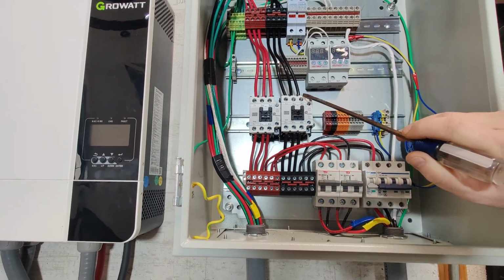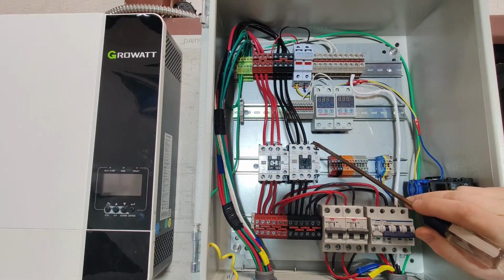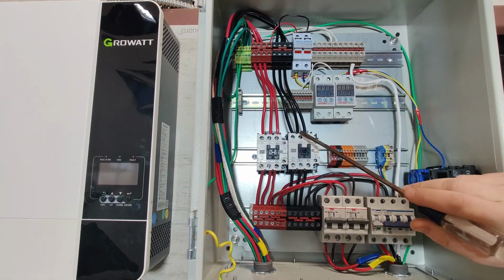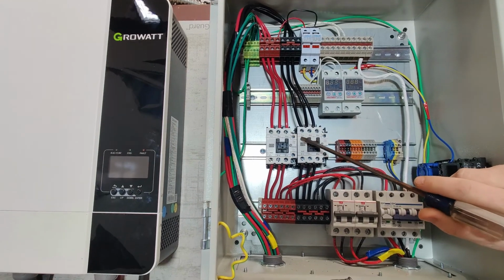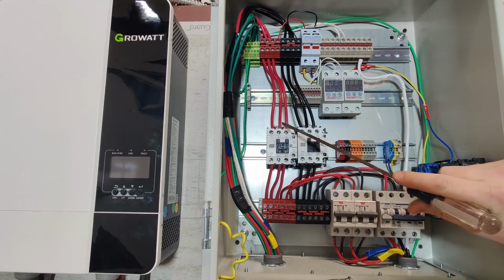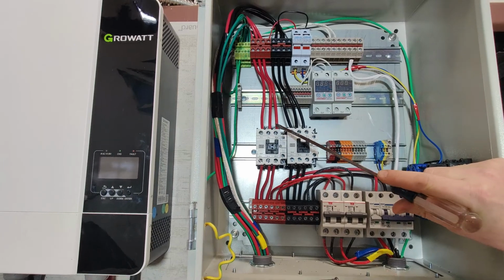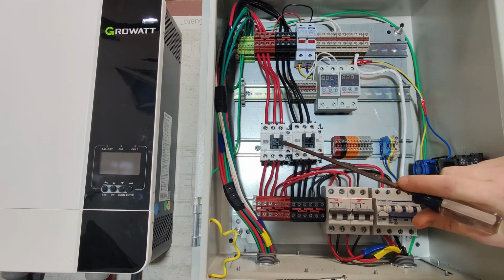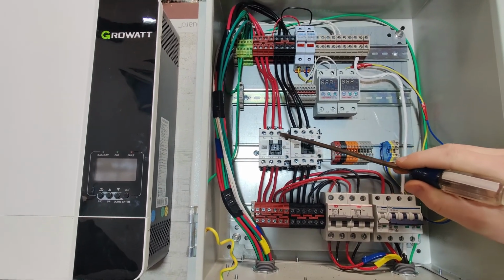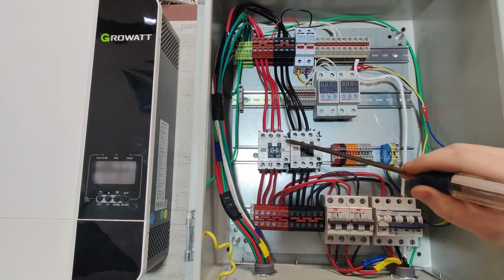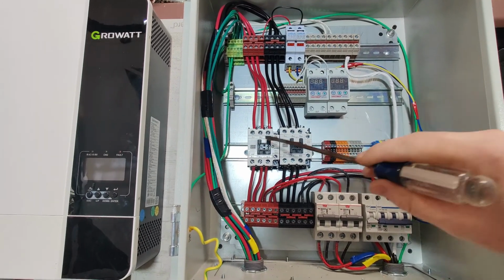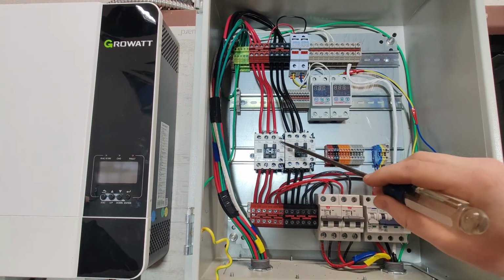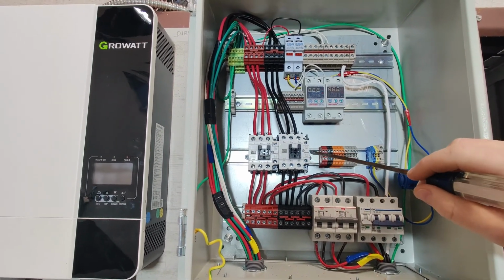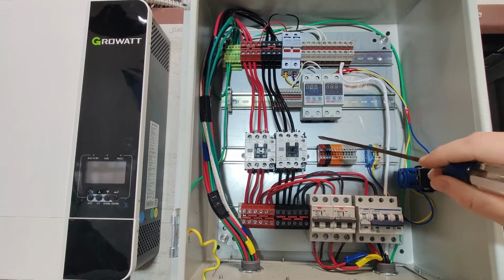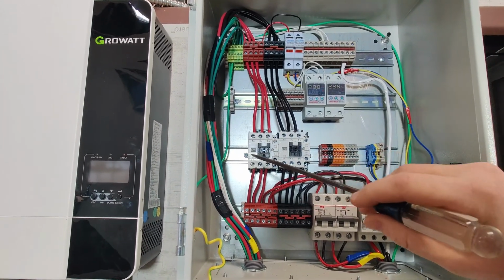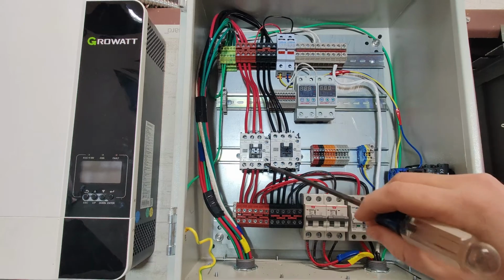I got this off a forum post where a guy said he was working at a company that built inverters, and their first generation of inverter had contactors like these, stacked up with red and then black both on the same contactor, and several contactors in the circuit. What happens is when you try to turn that off, the load gets shifted to the contactors that are still on, and it will end up burning out your final contactor.